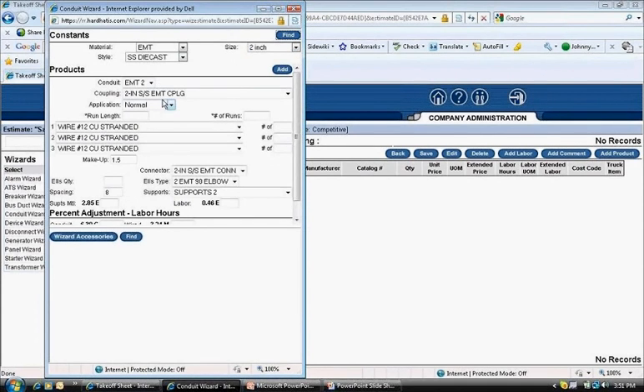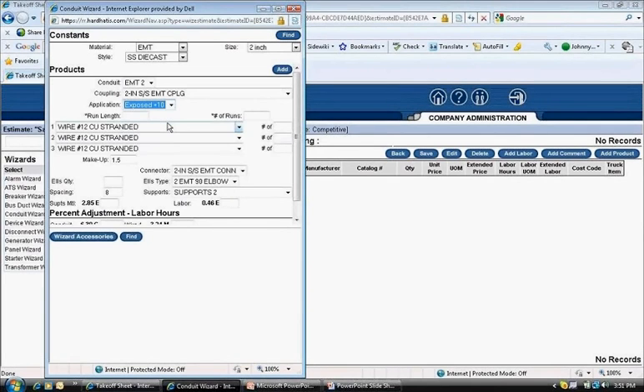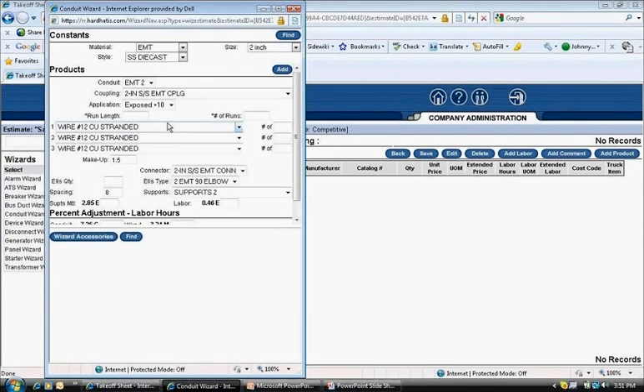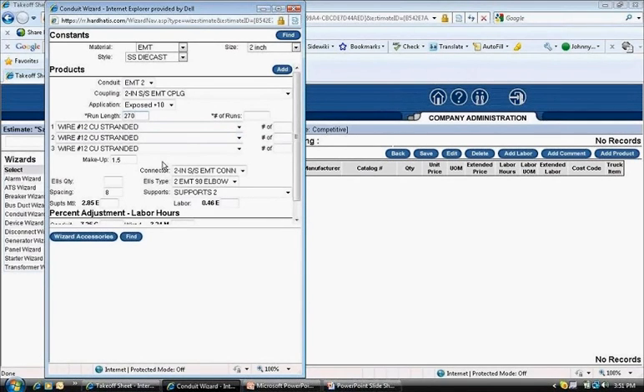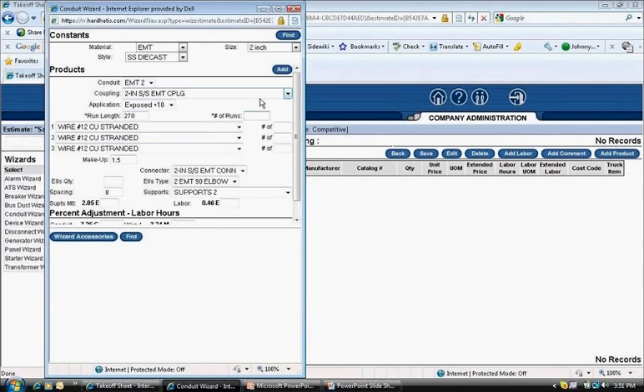I set the application at plus 10 feet like the conduit is to be installed above 10 feet off the floor. Again, applications refer to the level of difficulty of conduit run, and the program has more labor built in for more difficult runs. I click in the run length box and type in 270 for the total footage of conduit. I click in the number runs box and click in the number 2.